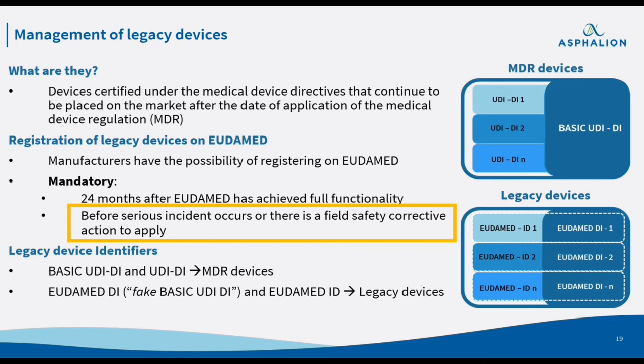Then we also have the EUDAMED ID, which is at the same level as the UDI. In this case, it also addresses the same fields as the UDI in Module 2 of EUDAMED. So legacy devices might already have a UDI, especially for those legacy devices which come from the USA, where there exists a similar coding system.